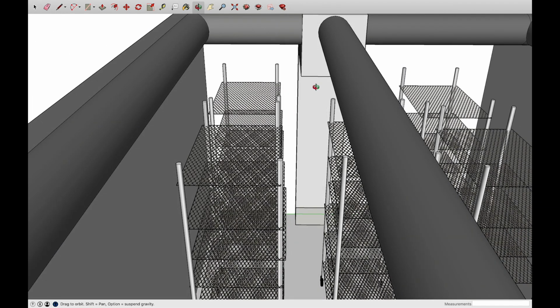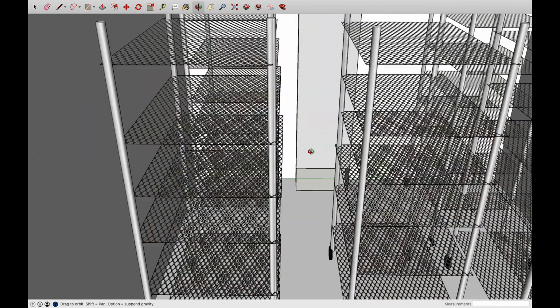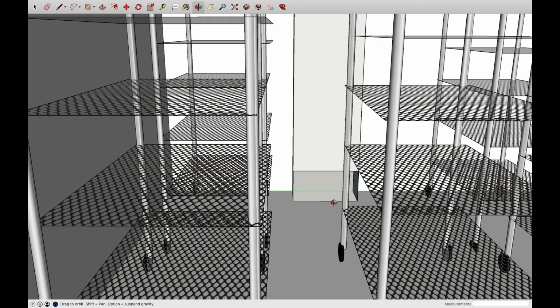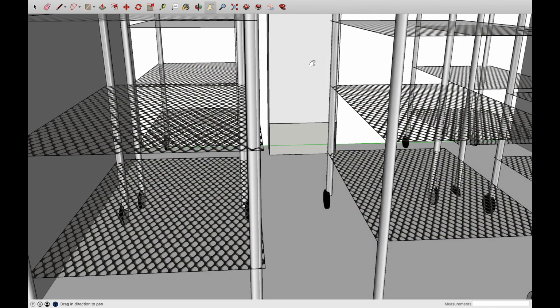And to ensure that we get that top to bottom effect that is so critical, especially in a rack type situation, we've done a custom return air plenum that you see that goes all the way down to the bottom, all the way to the floor. And so this is going to cause all the airflow to drop right down and then return right back into that return air, which is super important for what we're trying to do.